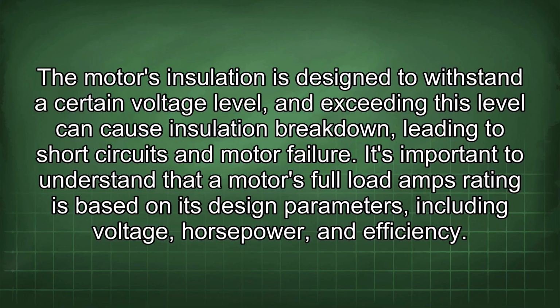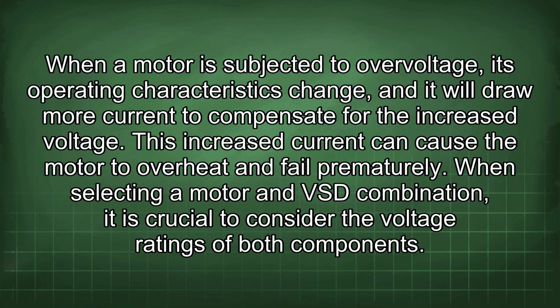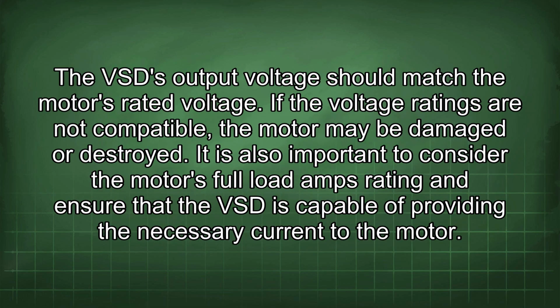It's important to understand that a motor's full load amps rating is based on its design parameters, including voltage, horsepower, and efficiency. When a motor is subjected to overvoltage, its operating characteristics change and it will draw more current to compensate for the increased voltage. This increased current can cause the motor to overheat and fail prematurely. When selecting a motor and VSD combination, it is crucial to consider the voltage ratings of both components. The VSD output voltage should match the motor's rated voltage. If the voltage ratings are not compatible, the motor may be damaged or destroyed.